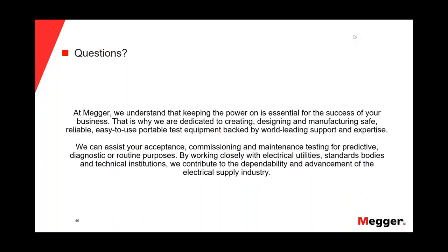Well, it depends. If you have some concern in the way the cable was brought to your facility, if maybe it was not the people of your company and you have no idea how they transported the cable from the factory to your facility, it will be good to do a PD test before connecting the splices and the terminations. But I will say that mainly if you have a major issue, maybe if they mishandled the cable during the transport, if you do the PD test with the splices and the terminations, you will be able to detect that problem.